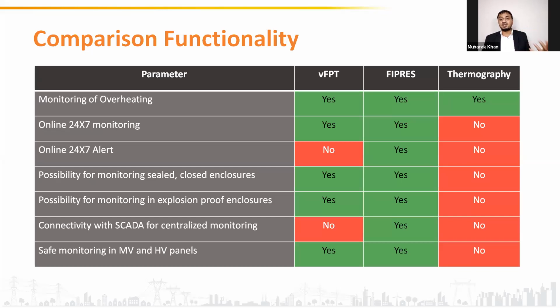But can we get a 24/7 alert in case of such explosion proof or sealed environments? We cannot get it using VFPT, but we can get it using the remote FIPRES. Can we connect to SCADA? Only FIPRES can be connected to SCADA or centralized monitoring, nothing else. Safe monitoring in MV and HV panels can be achieved only with VFPT or FIPRES, but not with thermography. With FIPRES, we get the additional functionality of remote alarm 24/7. Otherwise, 24/7 monitoring is already done in VFPT also.